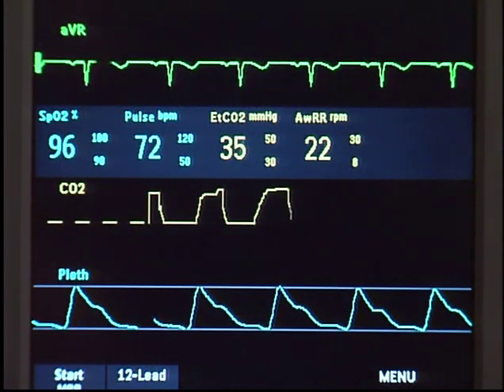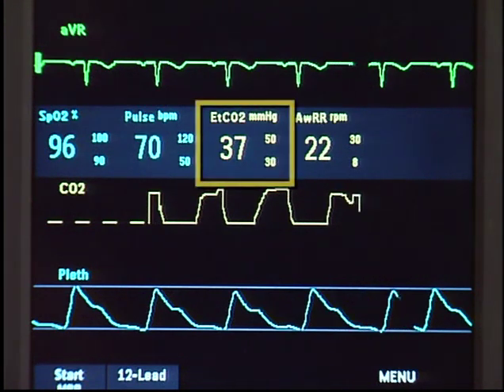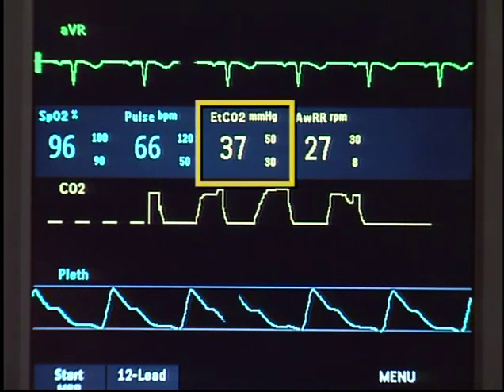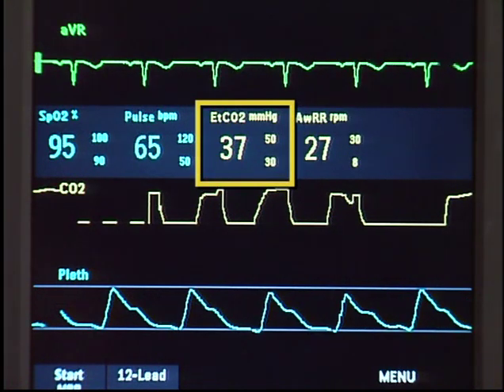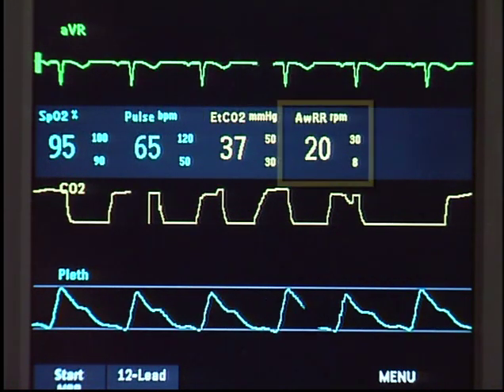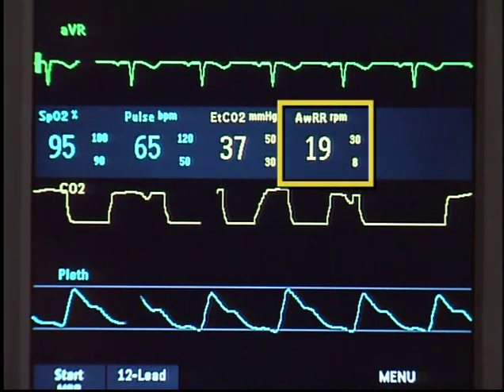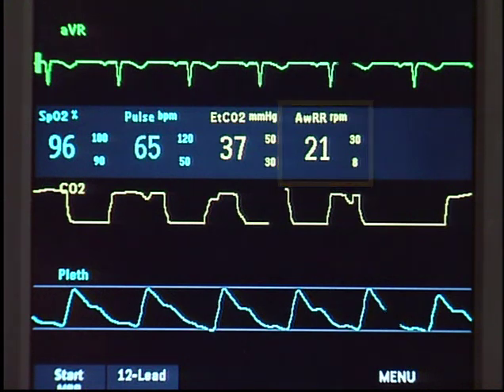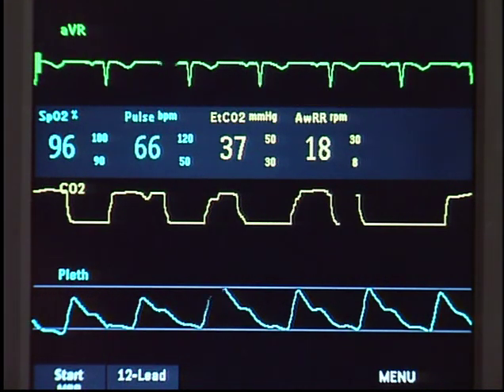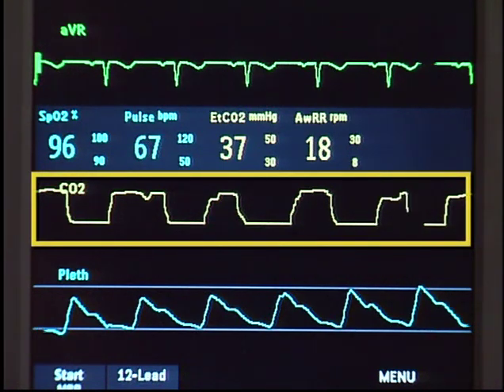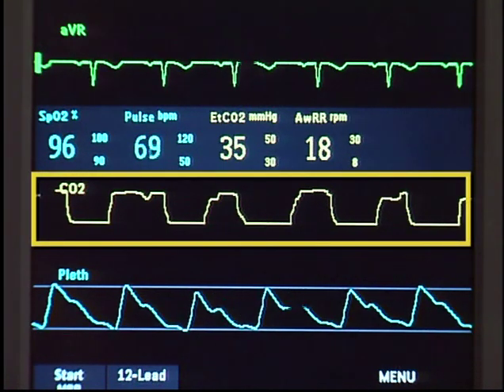There are two numerics associated with CO2 monitoring. The first, EtCO2 or end tidal carbon dioxide, is the peak CO2 value measured at the end of each expiration. The second is AWRR, airway respiration rate, the number of breaths per minute. In addition to the numerics, the monitor also displays the CO2 waveform or capnogram. This is the normal capnogram shape. It is important to note that on a capnogram, positive deflections represent expiration, whereas negative deflections represent inspiration, which is the opposite of most respiratory waveforms.